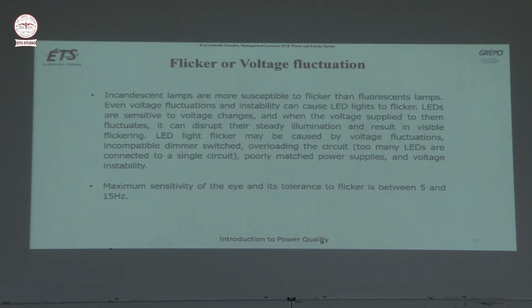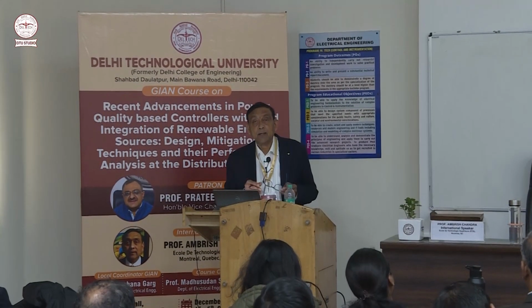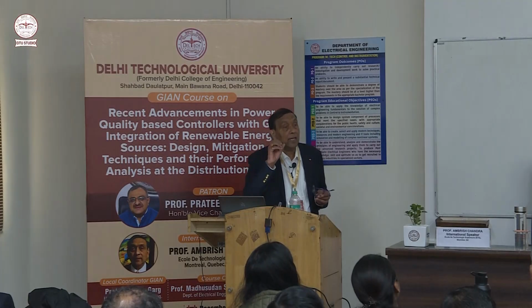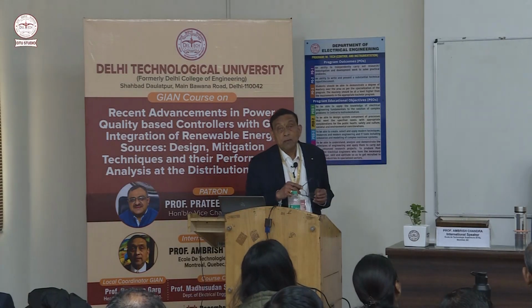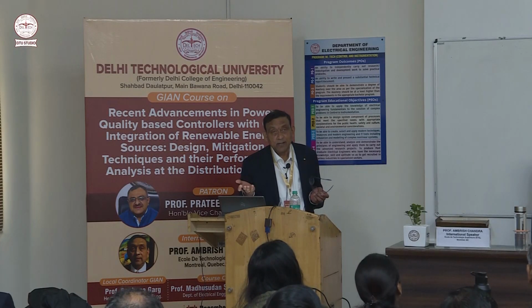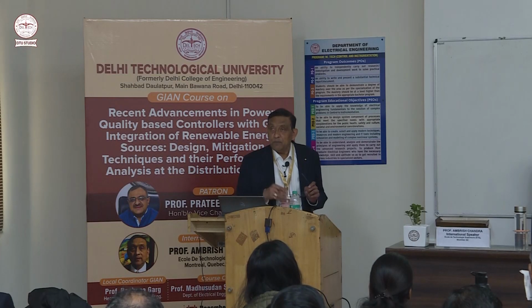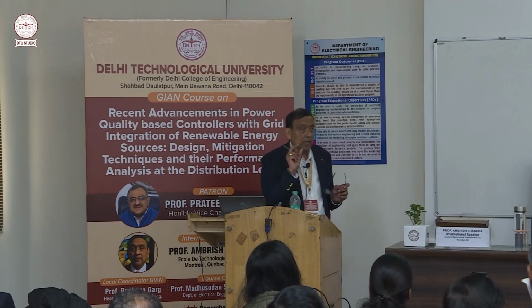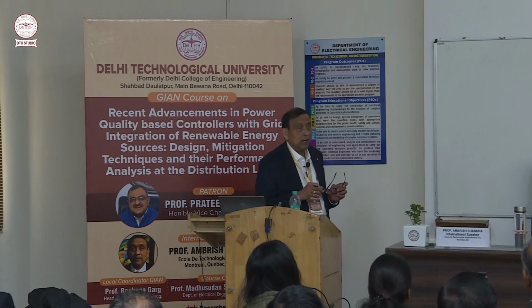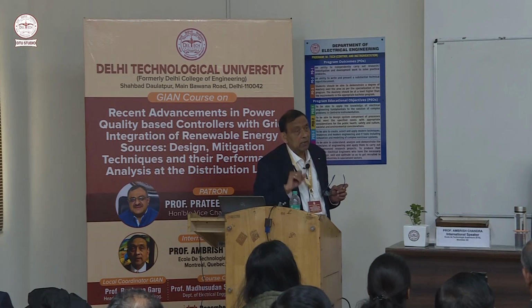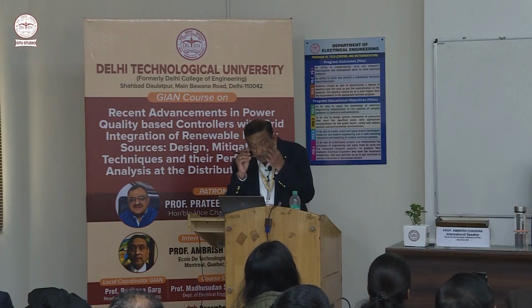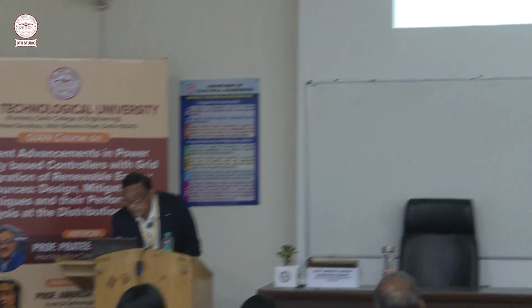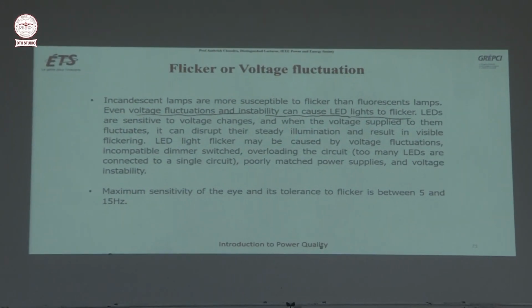So earlier we were thinking that voltage fluctuation, flicker, causes the incandescent lamp to blink like this. But finally, I found out that it affects LEDs also. Because once I brought an LED lamp and put it in my house and I used a dimmer, and at certain value I saw the LED lamps were also fluctuating. Even voltage fluctuation instability can cause LED lights to flicker. LEDs are sensitive to voltage changes, and when the voltage supply to them fluctuates, it can disrupt their steady illumination and result in visible flickering.